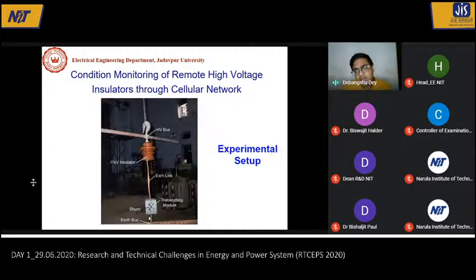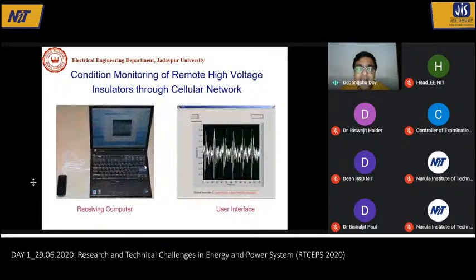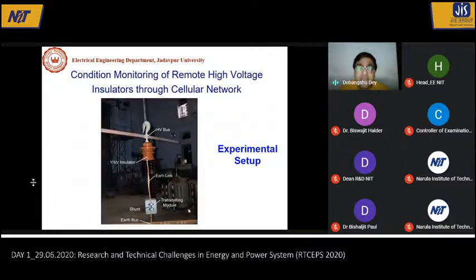So we have made one prototype for that. This is one insulator, and the lower one is the earth link or earth line. In the earth line we have set this particular module, and that module is acquiring the leakage current - the current that flows through the surface of the insulator to the ground. As this insulator has very high resistance, the surface leakage current will be very small, of the order of milliamperes or microamperes. So whenever you are recording that current, it gives you the condition of the insulator.